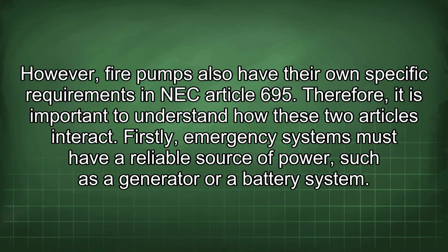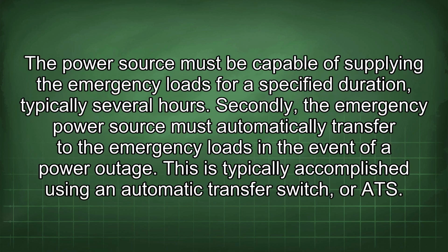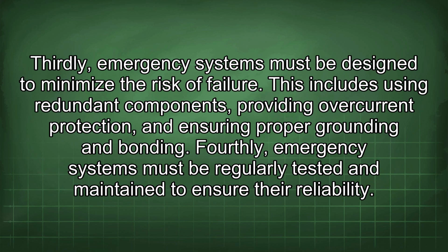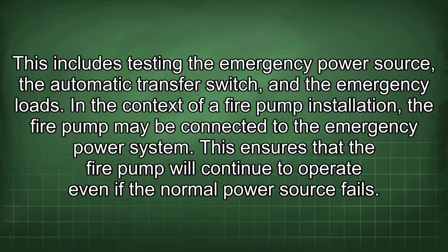Firstly, emergency systems must have a reliable source of power, such as a generator or a battery system. The power source must be capable of supplying the emergency loads for a specified duration, typically several hours. Secondly, the emergency power source must automatically transfer to the emergency loads in the event of a power outage. This is typically accomplished using an automatic transfer switch, or ATS. Thirdly, emergency systems must be designed to minimize the risk of failure. This includes using redundant components, providing overcurrent protection, and ensuring proper grounding and bonding. Fourthly, emergency systems must be regularly tested and maintained to ensure their reliability. This includes testing the emergency power source, the automatic transfer switch, and the emergency loads.